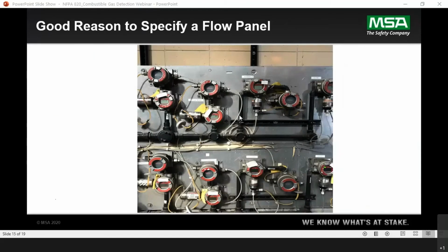So here's a good reason to specify a flow panel, if you will. This was an actual picture taken in the New York metro area, but you can see that the user ended up buying loose sensors and gas monitors and pumps, and you can see the spaghetti wiring. The flow panel can actually do much better to improve this in terms of the installation.